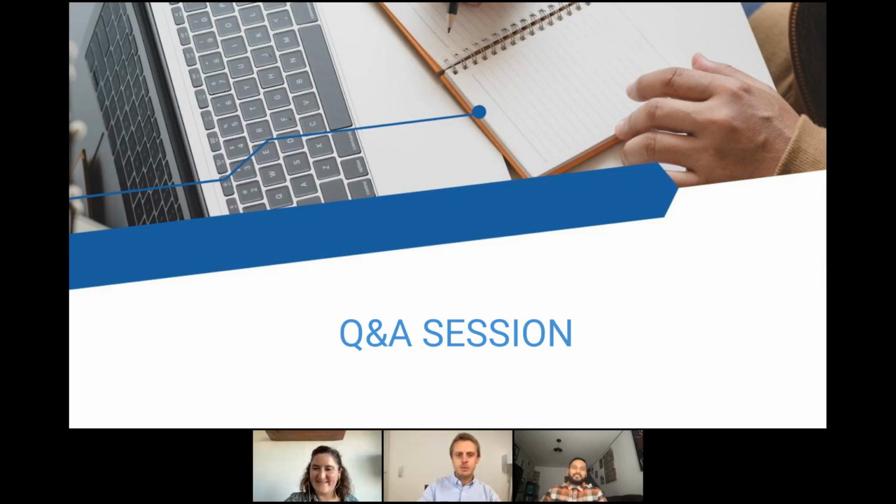So the question was, if you have an MDD certificate, do you still have to start PMCF activities, right? So actually, yes, you have to do it. It's stated in Article 10 of the MDR. So even if you have an MDD certificate, you now have to have a PMS, which includes PMCF activities. This would be good for you to start already, because at the latest in 2024 you have to have data available. So yes, you have to start doing it now. This is actually a requirement already.